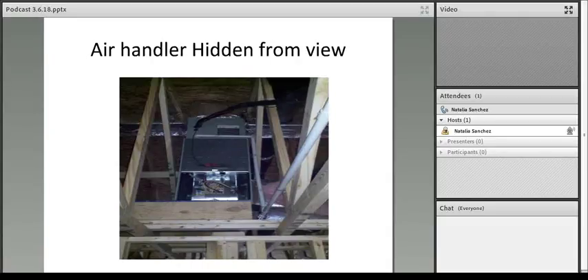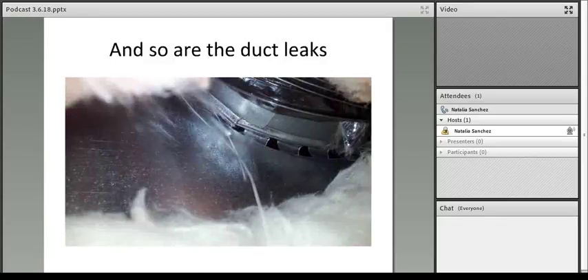So here's a builder who was putting a second floor in a house, and when I visited, simple solution, hide the air handler in the attic. I don't have to deal with it. I get all that usable space, and I also get to hide all the duct leaks. And that is a 6-inch round duct with probably 20 little holes that are about 1/8 of an inch square. There's probably 15 holes around that circumference of that fitting. That's a terrible thing to do, and that was built 8 years ago, and it shouldn't be there. Right. But it is, and it will be there for the rest of that home's life.